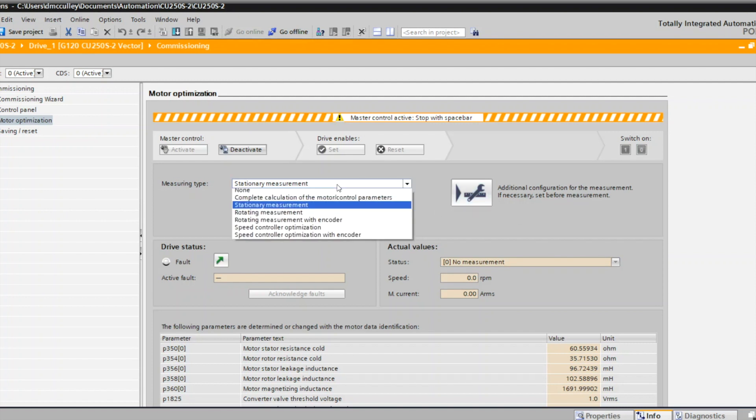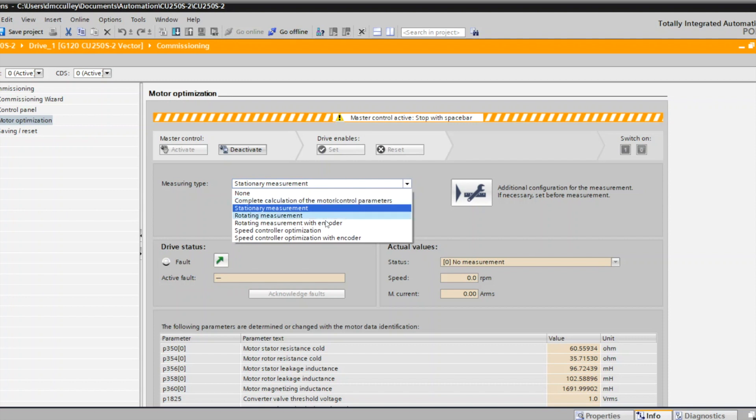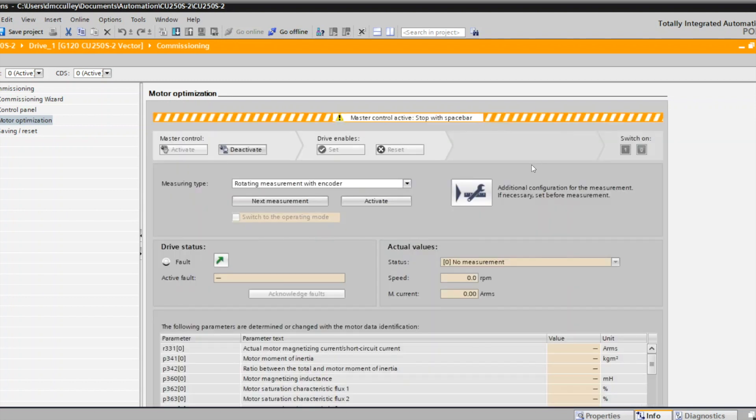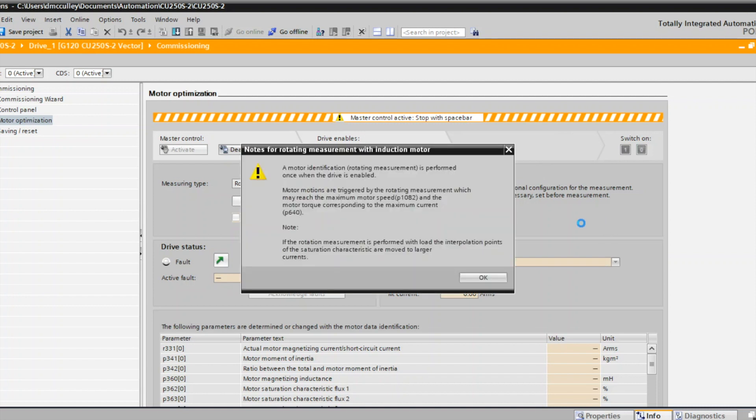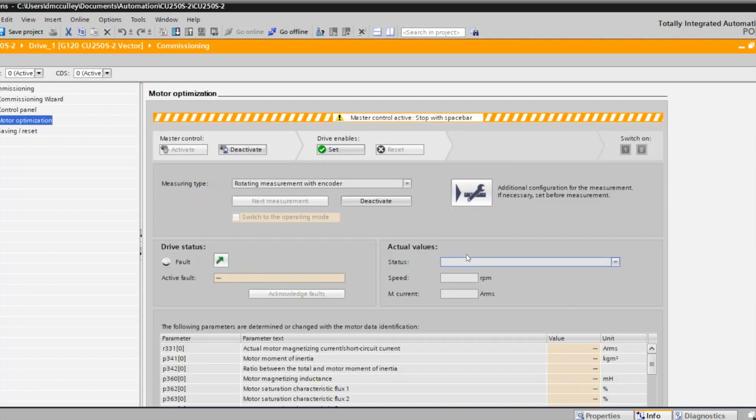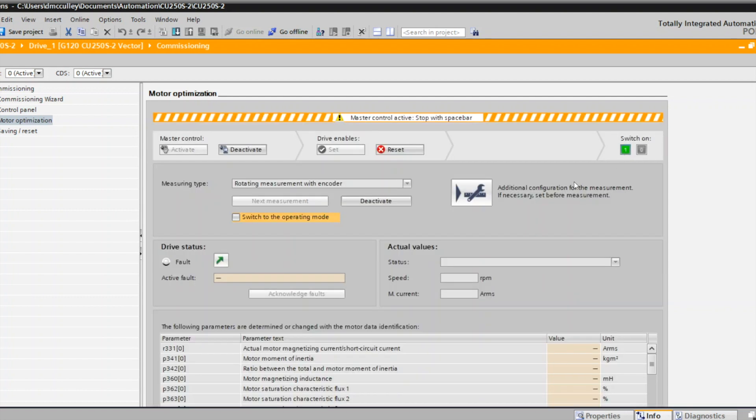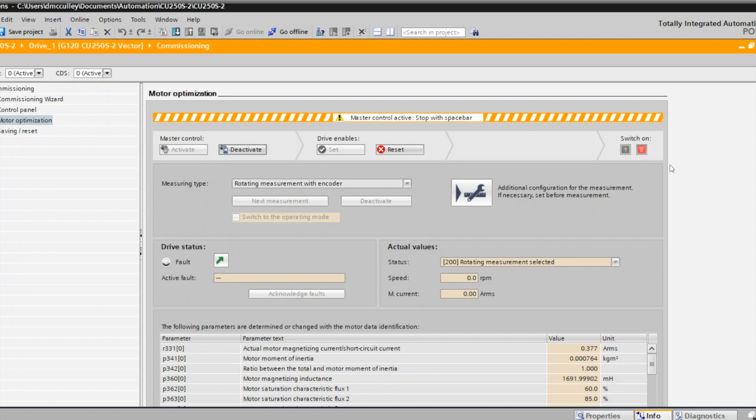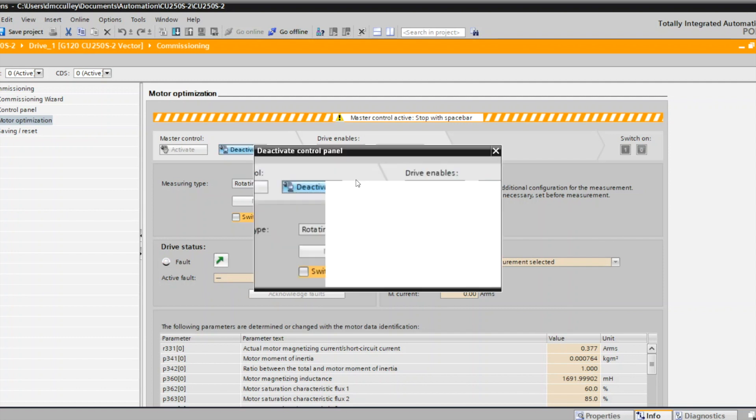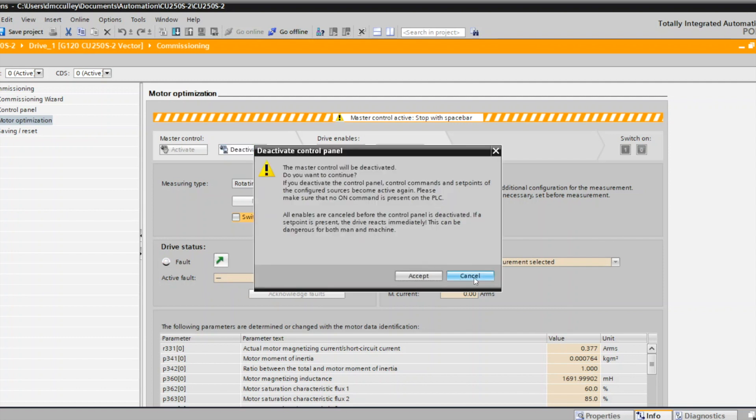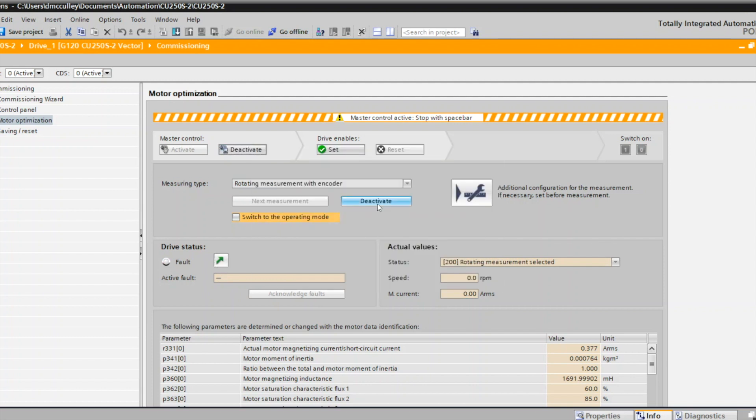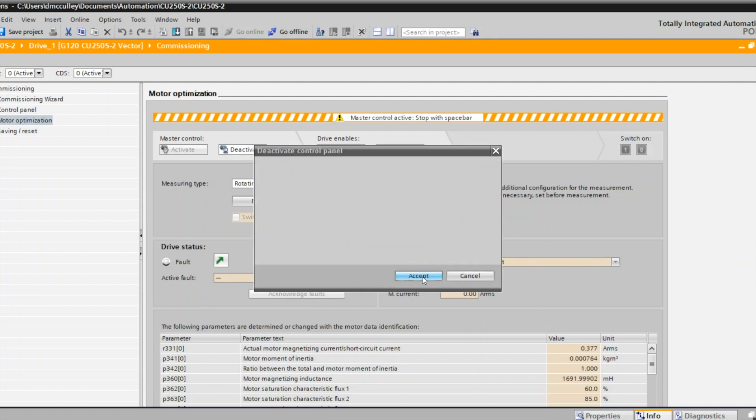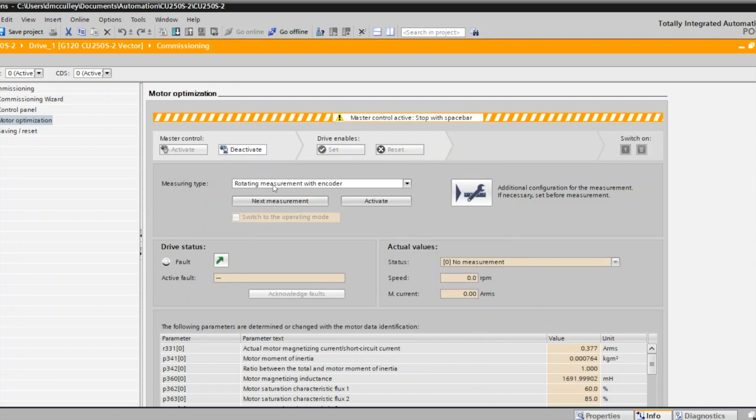The next measurement I would want to do with an encoder is the rotating measurement or vector control. Activate that measurement and set the enable and then perform that. Again, it's a rotating measurement, so your motor is going to turn, so you need to make sure everything's safe to do that. Once it's done, it'll stop. Again, since I don't have a motor, it might fault out. Just acknowledge that, and deactivate the measurement, which you shouldn't have to do. Deactivate control.